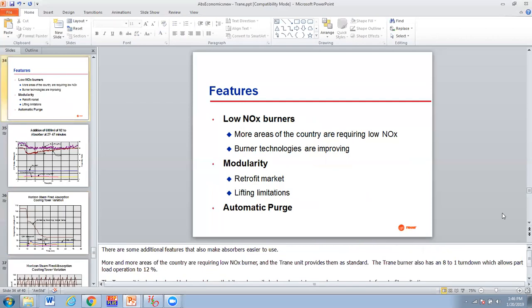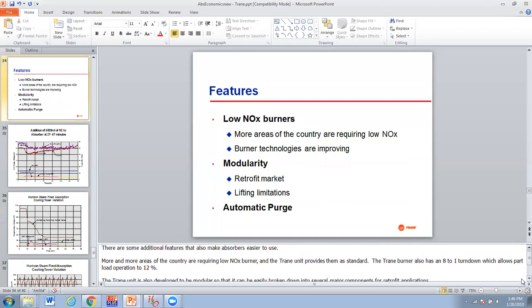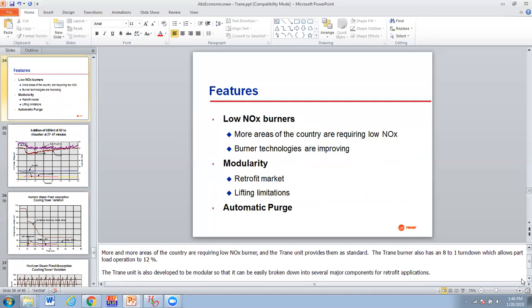Okay, other features. With all the environmental interest today, some other features have been added. You can get low NOx burners to reduce the emission of oxides of nitrogen from the combustion of the natural gas. Trane provides them as a standard. And again, the Trane burner has an 8-to-1 turn down. It gets you down to 12% operation, which is pretty good.